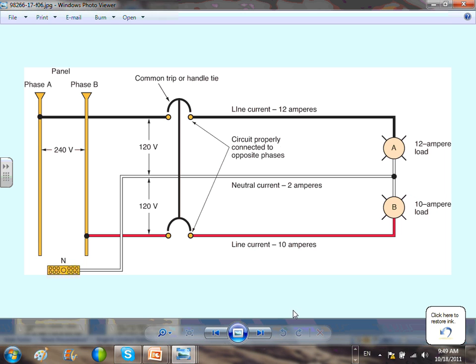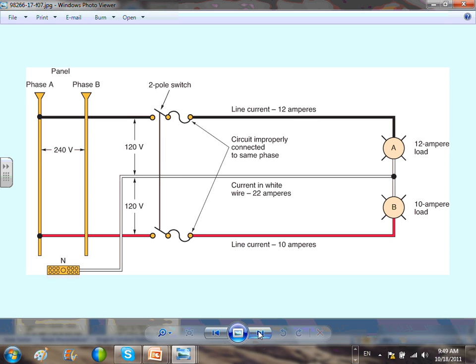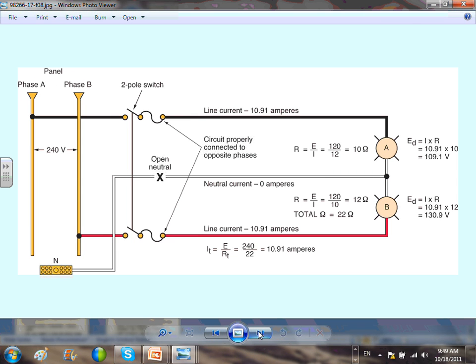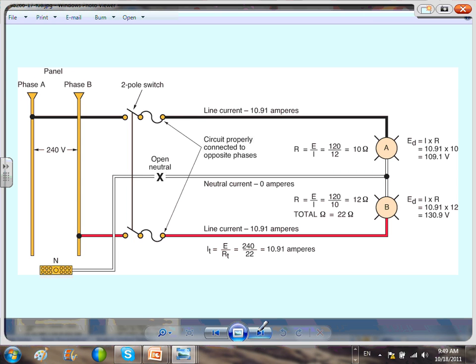What's the problem with multi-wire branch circuits? Multi-wire branch circuit, guys, you have to tie them together. Can you guys see how these circuit breakers are tied together? Now, let me just take you through this example. This is a really nice example of what happens if you open a neutral. If you open the neutral, guys, first you need to find the resistor for each load. There's a resistor for each load, right? And then from the resistor, from the 240, look, can you guys see that these two are sharing 240 now, as if the neutral does not exist here? So that will get you 10. Right.